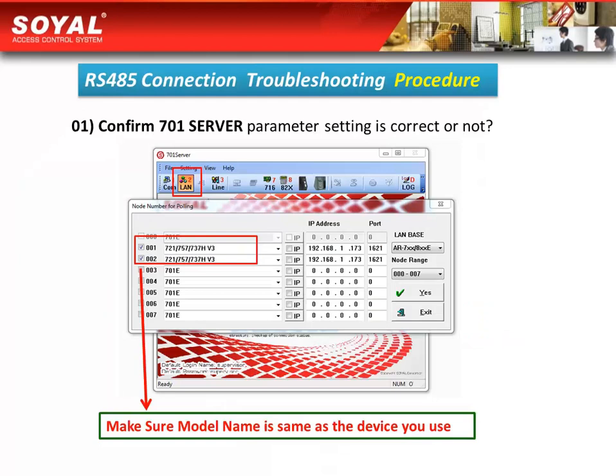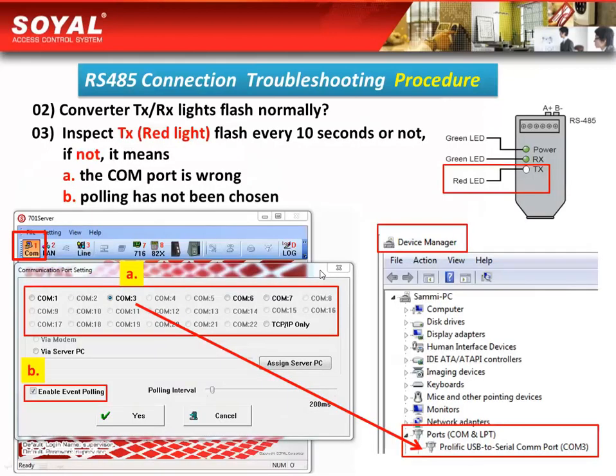If you find that your RS485 connection is unsuccessful, here are the solutions. First, go to confirm that the 701 server parameter settings are correct, and make sure that the model name you chose is correct. Second, observe the converter's TX or RX light to check whether it is flashing normally.